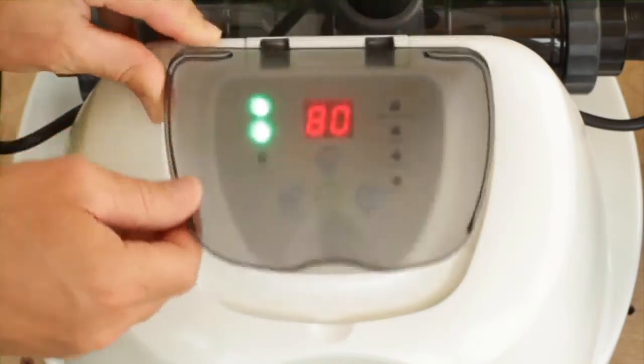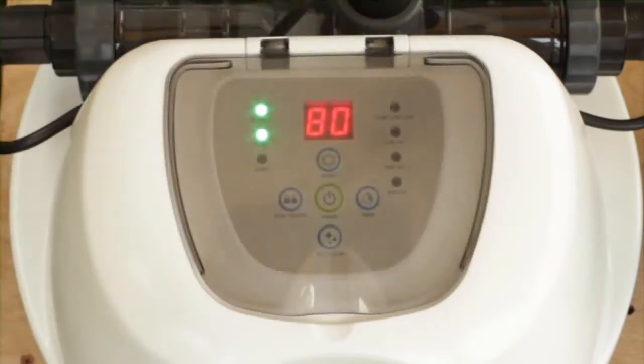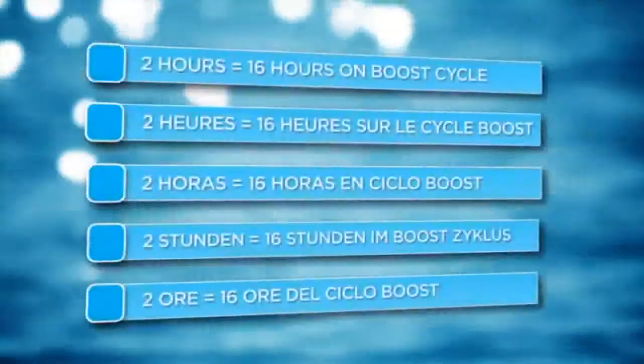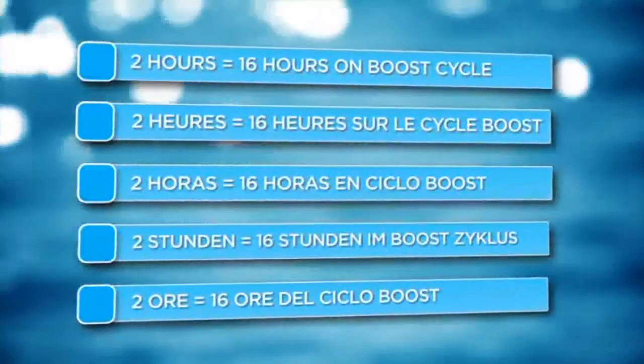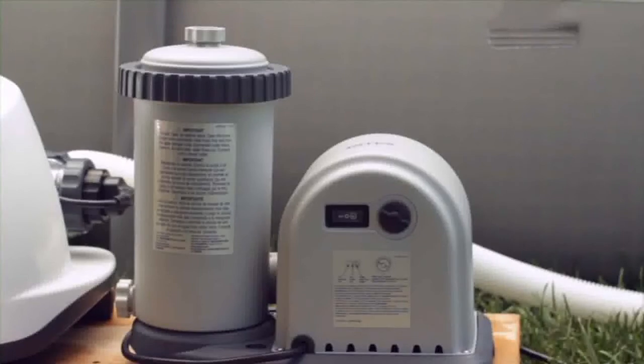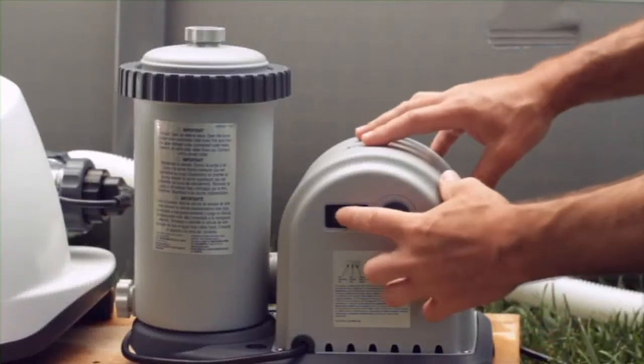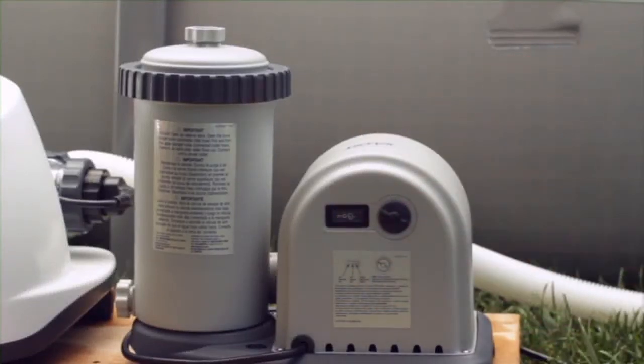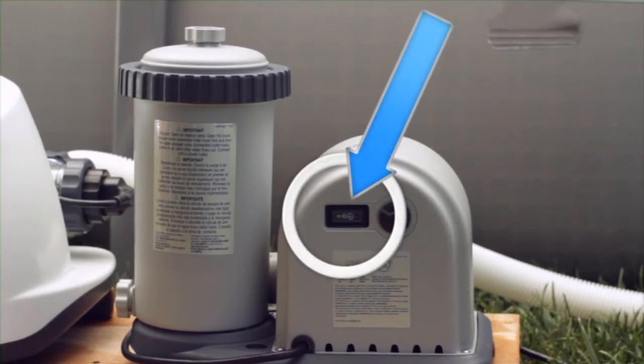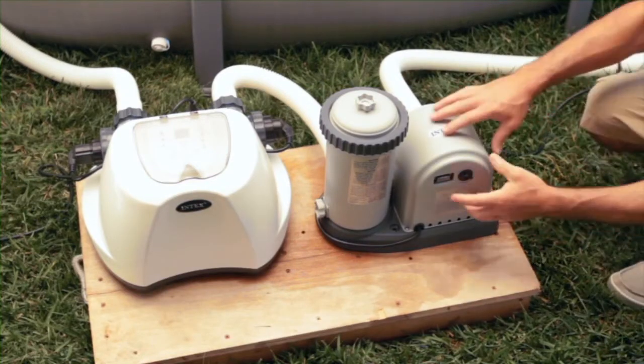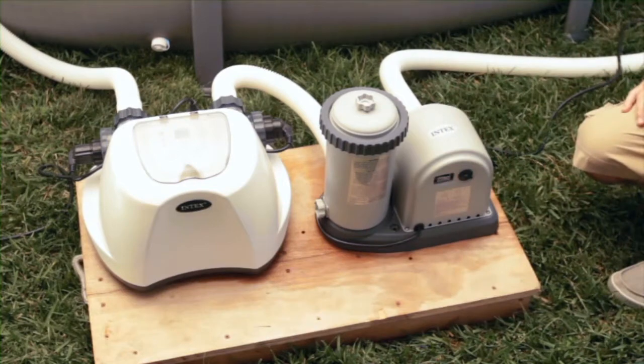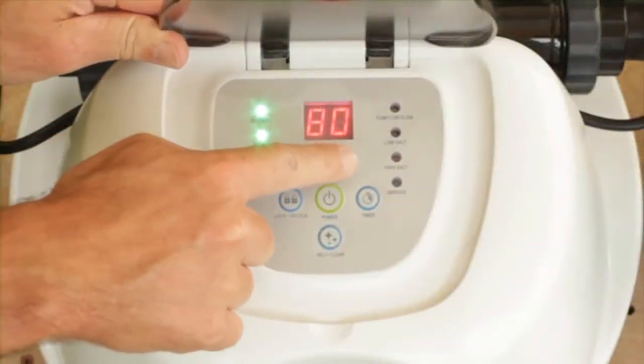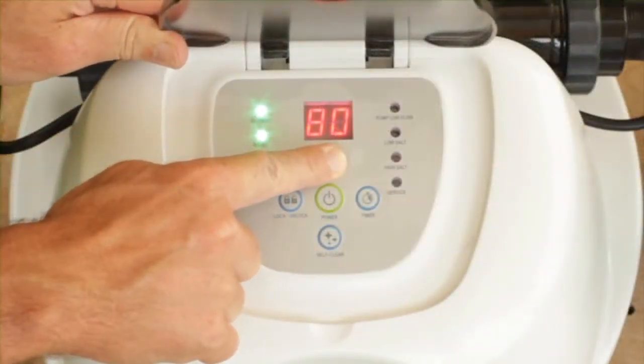The boost cycle runs 8 times longer than the programmed operating hours. If your system has been set to run for 2 hours, the boost cycle will run for 16 hours. Set your filter pump to run continuously during the boost cycle. A filter pump with a timer should be switched from timer to on for the duration of the boost cycle. Remember to start your filter pump 5 minutes before running the boost cycle. You may cancel the boost cycle at any time by pressing and holding the boost button for 5 seconds.